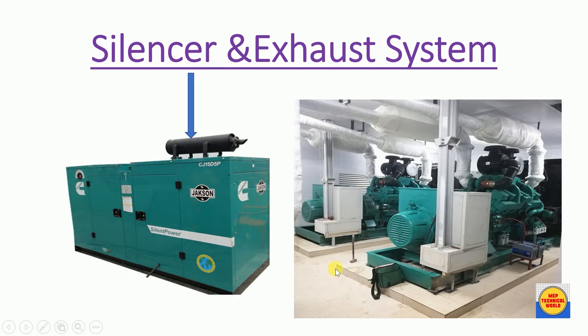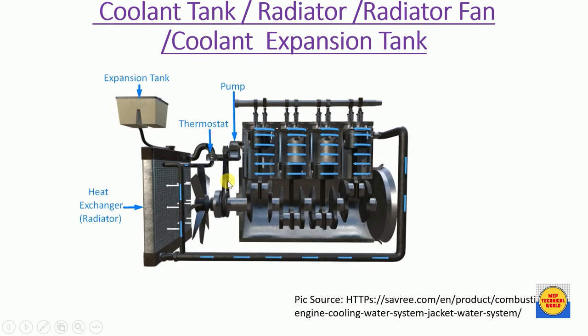Next is the cooling system of the DG. It consists of a coolant expansion tank, a heat exchanger (radiator), a thermostatic valve, a coolant pump, and a radiator fan driven by the crankshaft of the engine. The cooling system maintains the engine temperature at 80 degrees Celsius.